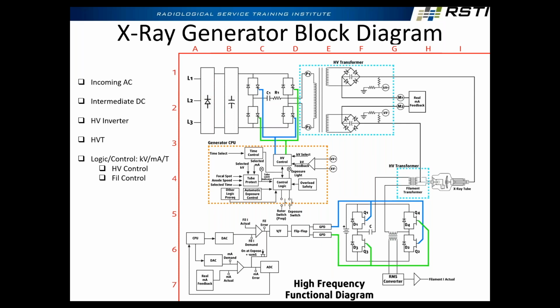I mean, the difference between this and when you add CT into the mix, what's the big thing that has to change with CT? It's spinning. It's rotating around, taking axial slices of the body. So where's the challenge here? How do I get this on a turning gantry? What vendors usually will do is put a slip ring either here or here. So now I'm going to pass that voltage on brushes onto a rotating ring that literally drags along the rotating side and passes that voltage.